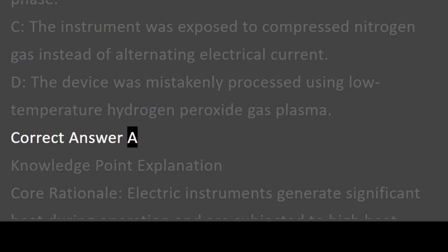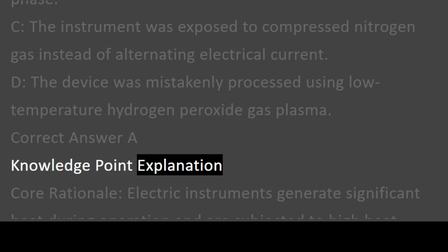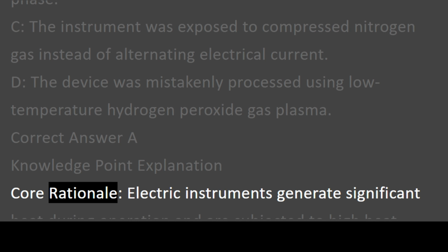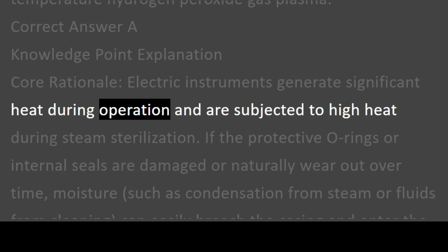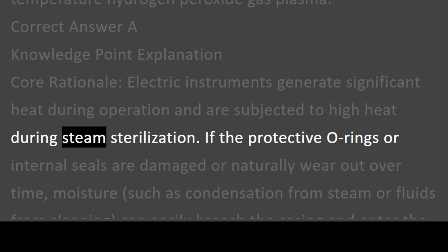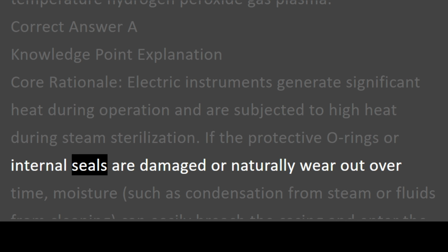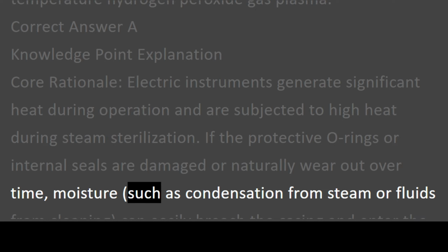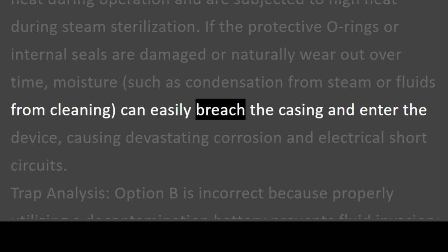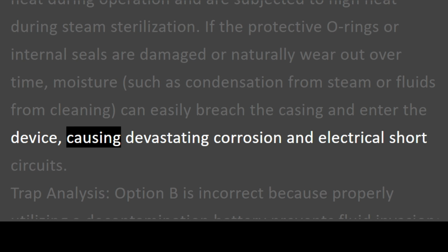Correct answer: A. Knowledge point explanation. Core rationale: electric instruments generate significant heat during operation and are subjected to high heat during steam sterilization. If the protective O-rings or internal seals are damaged or naturally wear out over time, moisture, such as condensation from steam or fluids from cleaning, can easily breach the casing and enter the device, causing devastating corrosion and electrical short circuits.